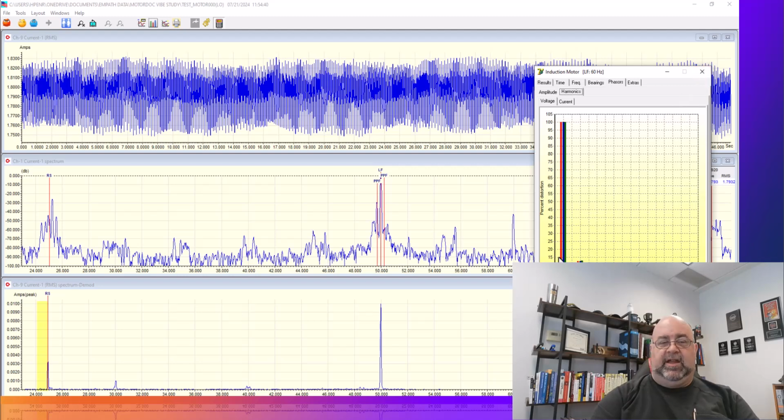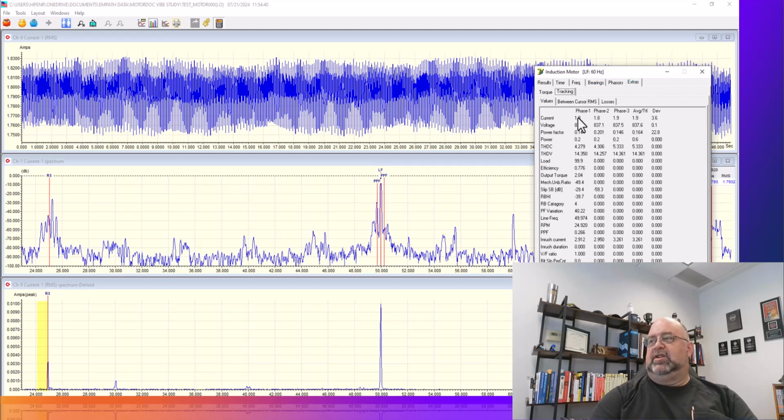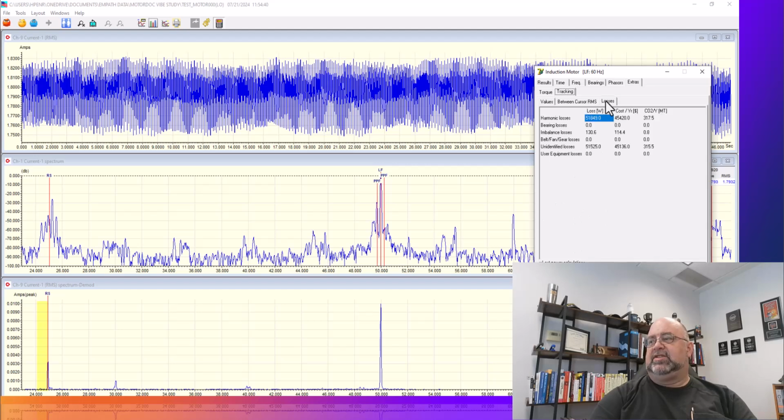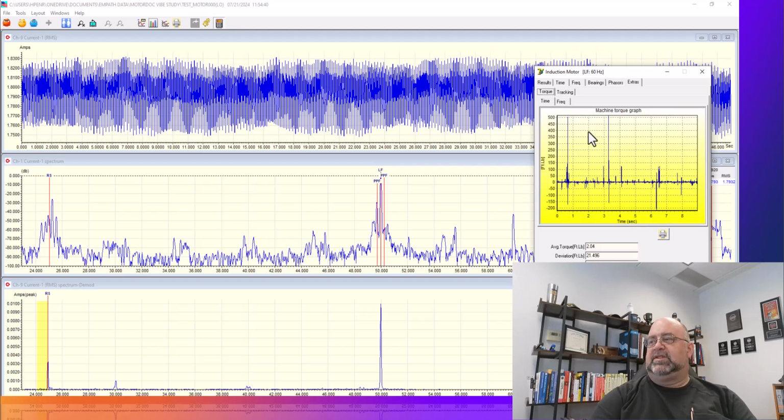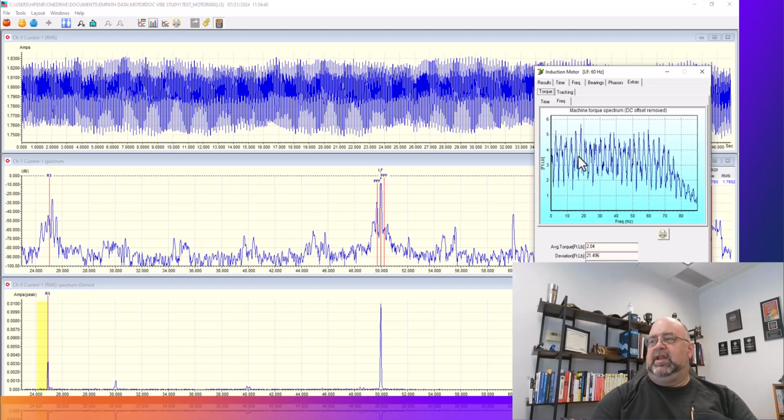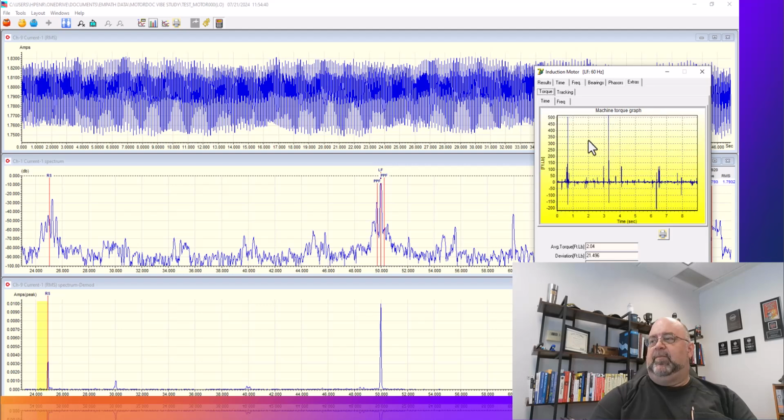There had better be high harmonics in voltage, because they pretty much almost have a square wave. Extras, I can take a look at any losses associated with any defects, and that'll calculate my total losses. I can look at the time waveform frequency. This is basically, that's not time waveform. This is time waveform. This would be everything else. Because everything's so low, it's not doing the greatest.